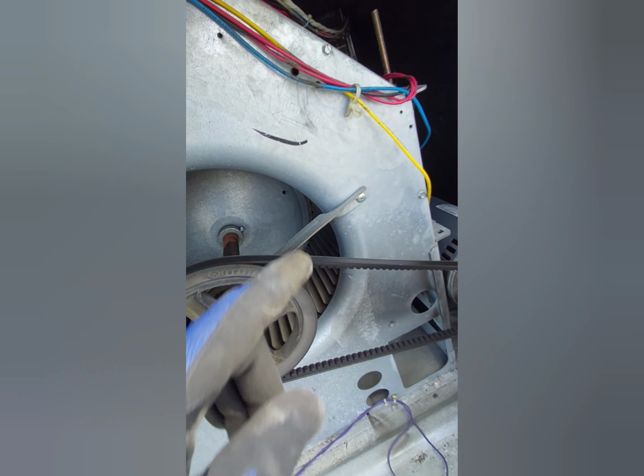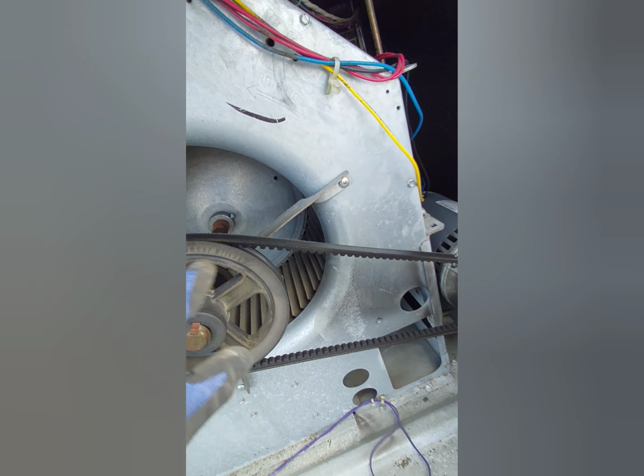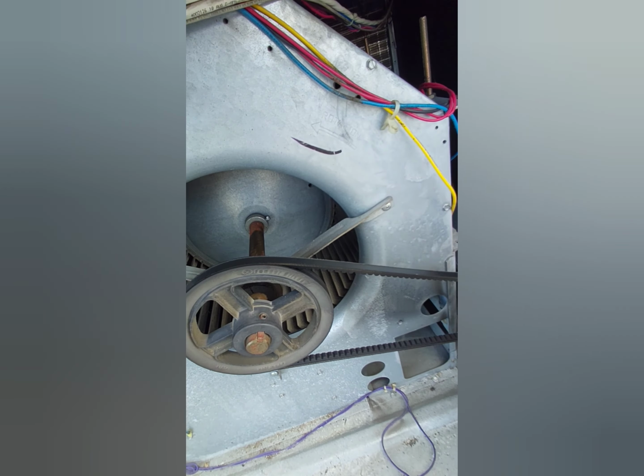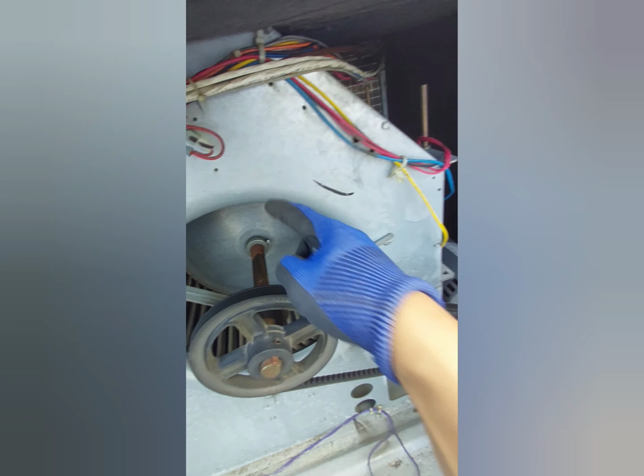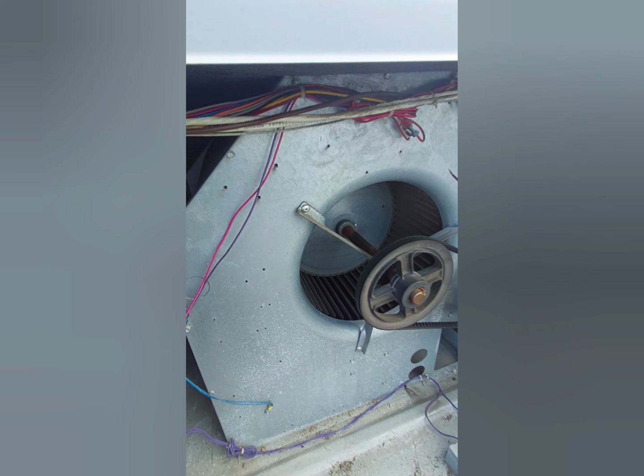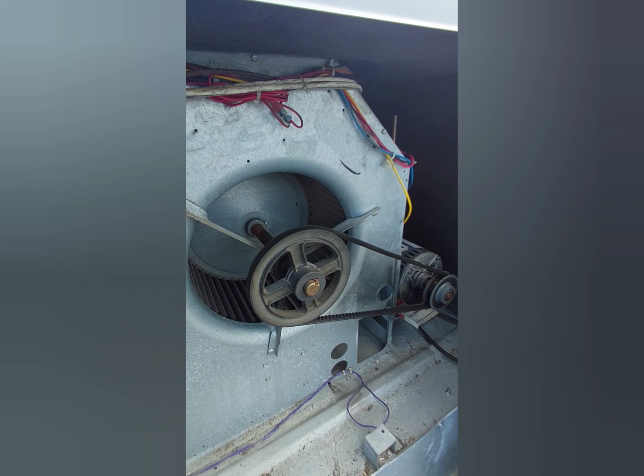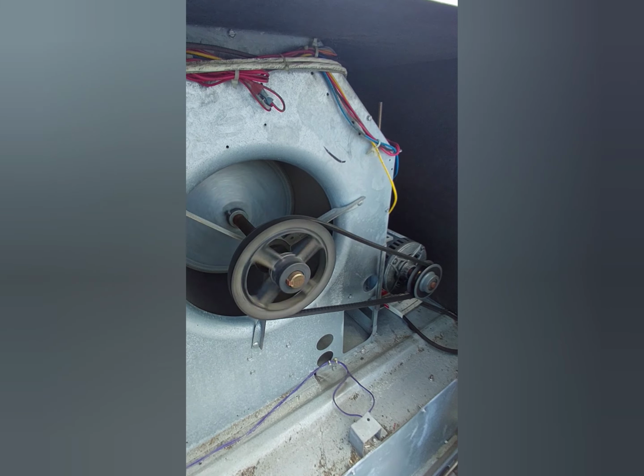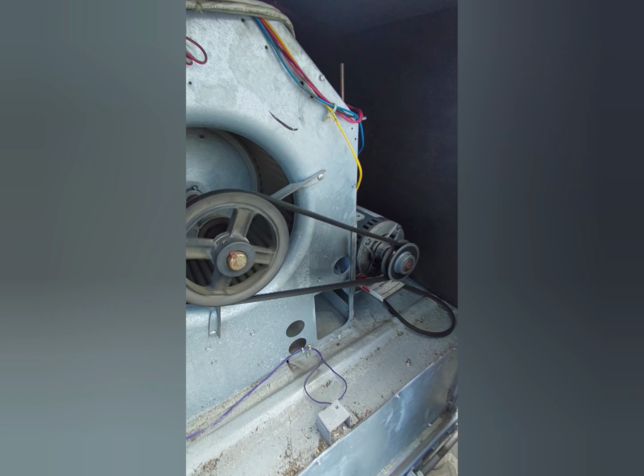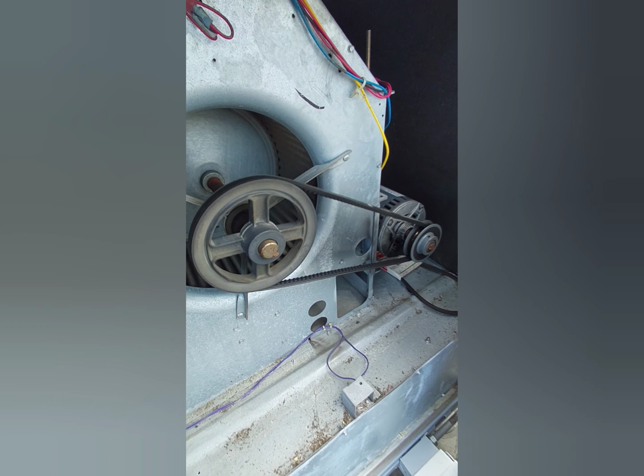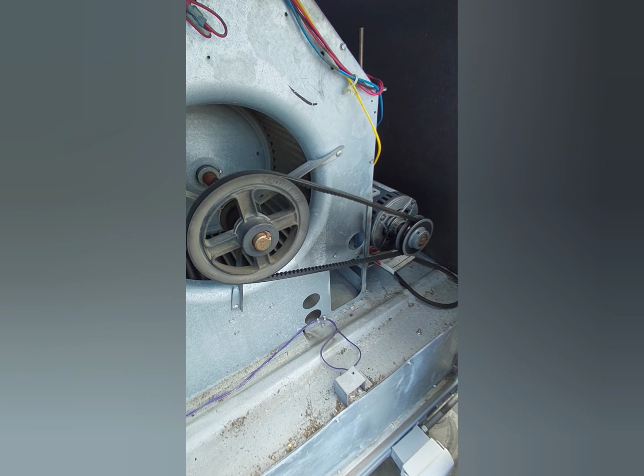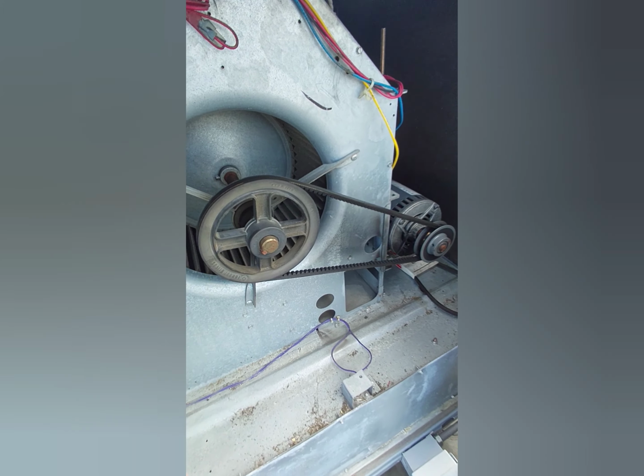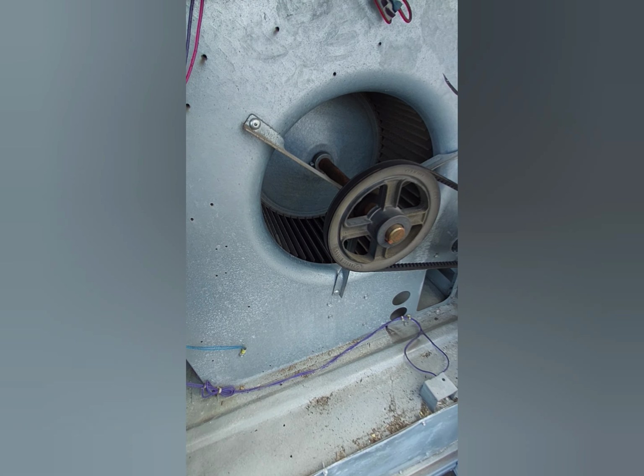So the direction of the blower, mind you the power is on now, so this can cut on any time, so be careful when y'all touching this stuff. The rotation of the fan goes that way, so we're just gonna hit the contactor, and you can't see it on the screen, but if it slows down, you can see it's going in the right direction. It's supposed to be going in that direction, and it's doing that.